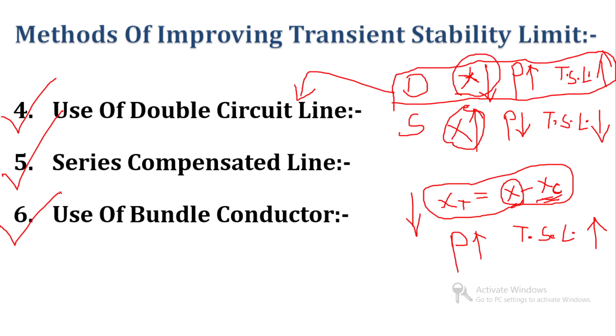Now the sixth point is the use of bundle conductors. We already know that bundle conductors reduce the reactance of the transmission line, so that will also improve the power transfer capability of the line, and in that manner we can improve the transient stability limit.